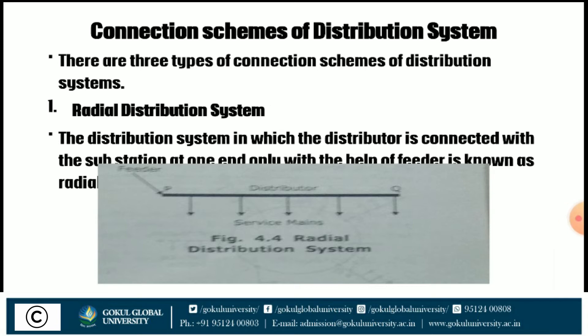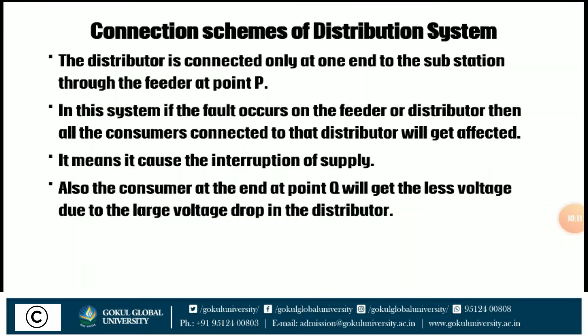Now we discuss the different connection schemes of distribution systems. First is the radial distribution system. The distribution system in which the distributor is connected to the substation at one end only with the help of a feeder is known as the radial distribution system. In this system, if a fault occurs on the feeder or distributor, all consumers connected to that distributor get affected — there is an interruption of supply. Also, the consumer at the far end will get less voltage due to the large voltage drop in the distributor.